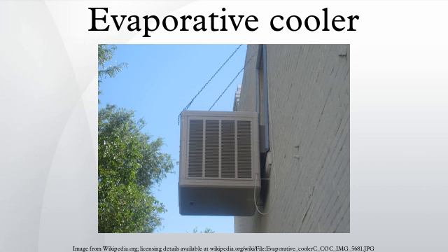According to the formula above, at 85% efficiency air may be cooled only down to 28.2 degrees, which makes it quite impractical. Comparison to air conditioning. Comparison of evaporative cooling to phase change air conditioning. Advantages: less expensive to install. Estimated cost for installation is about half that of central refrigerated air conditioning.